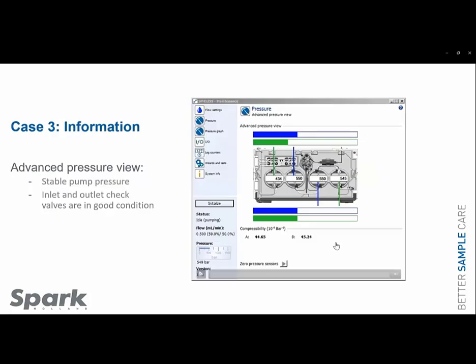We gather information. In the advanced pressure view, we check for 50-50% AB how the pressure looks and how the loading strokes of the primary pump heads are. Well, we see a stable system pressure. We also notice that the primary pump heads are 6 bar below the system pressure. The loading strokes are doing fine.